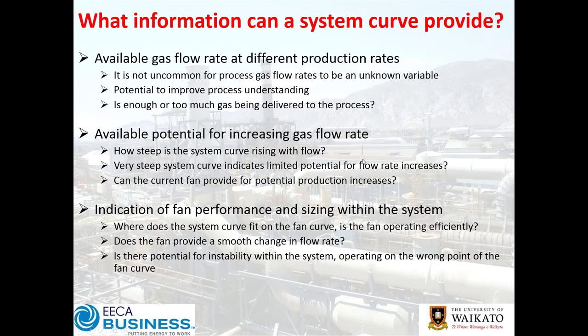How steep is the system curve as flow increases? If it's very steep, we have limited potential to increase our flow rate. If it's relatively flat, there's room to move. Where does the system curve fit on the fan curve — is the fan operating efficiently? Does the fan provide a smooth change in flow rate as pressure changes, or is control very unsteady and unstable? Understanding the system curve should help identify where the problems arise.